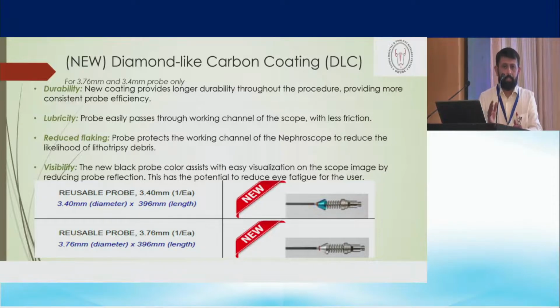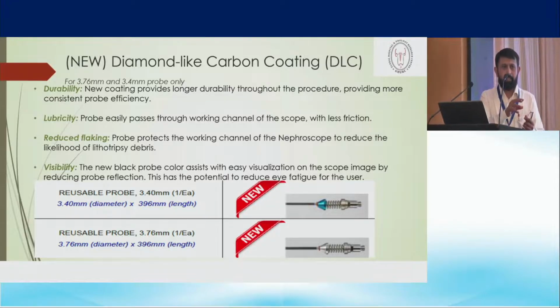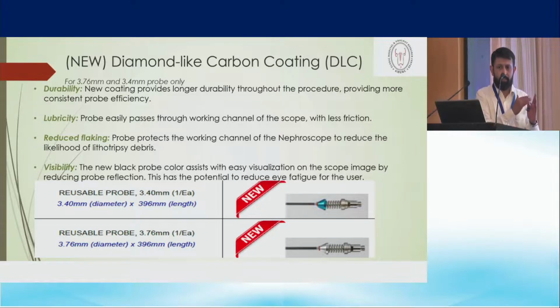The company has made a little change in the probes recently. They have come up with the DLC probe, which we used yesterday, the 3.4 mm. It is a black color probe. The advantage is increased durability, because they are reusable, but to a certain extent. If you saw my movement yesterday, if you move the probe a little bit, the camera moves because it is snugly fitting. These DLC probes have better lubrication, so once we move the probe, the lens does not move. There is reduced flaking, meaning the lateral damage has decreased with this improvement. Visibility is better when there is some blood, so the light reflection is less. The initial probes were stainless steel color. They have now got a black color so that they can be seen better at times of bleeding. This is the advantage of these DLC probes.